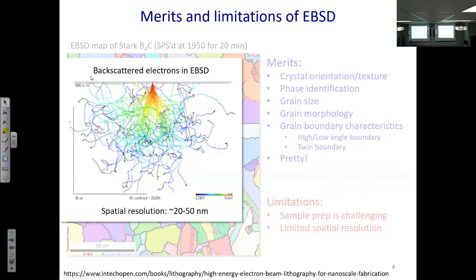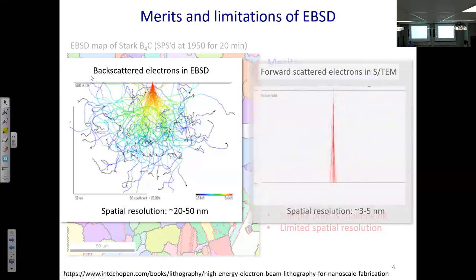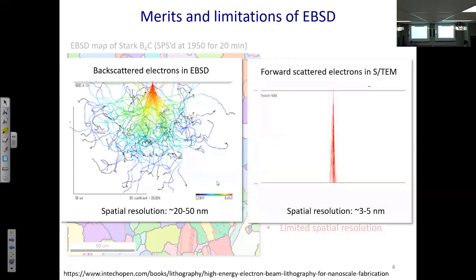In contrast, in TEM — transmission electron microscopy — samples are typically 100 nanometers thick, so beam broadening is quite limited, giving spatial resolution of 3–5 nanometers — a 10× improvement over EBSD. SEM can be thought of as a surface technique: you throw electrons at the surface and capture what bounces back, like ping pong balls. TEM, on the other hand, transmits the electron beam through the specimen, casting a shadow, and we work backwards from that shadow to understand the internal structure.